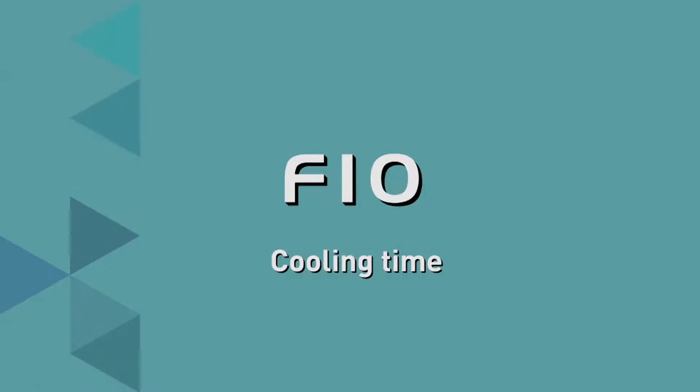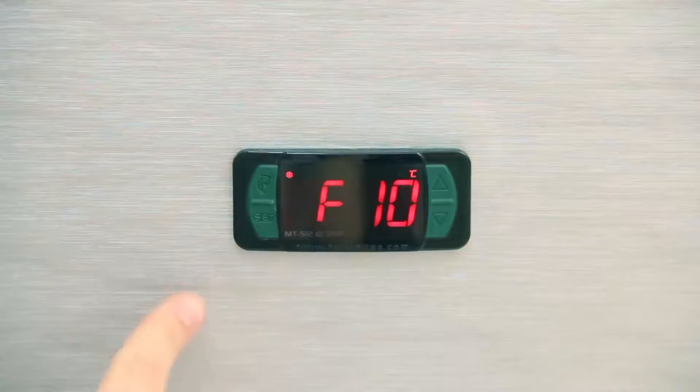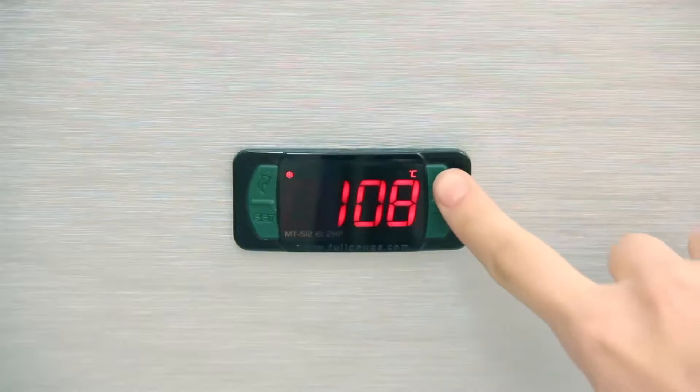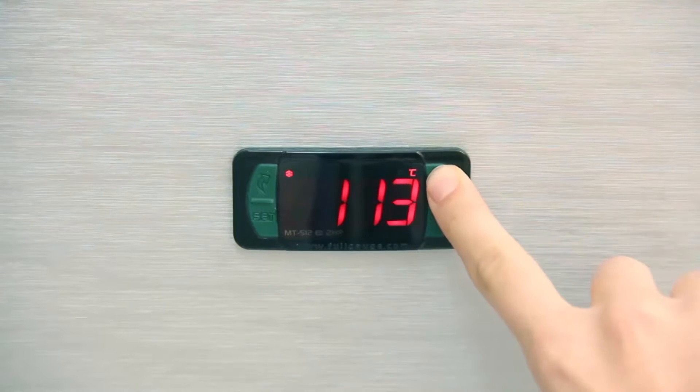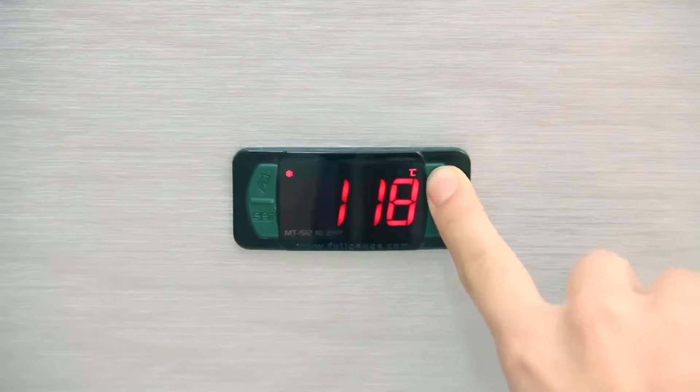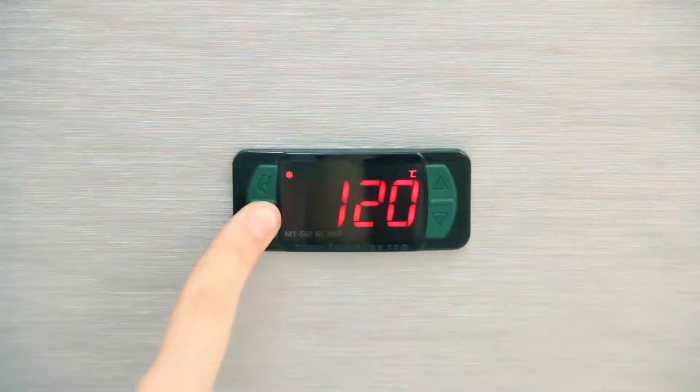F10, Cooling Time. It determines the minimum time the controller will act in cooling, that is, the interval between defrosts. In this example, we determined a time of 120 minutes.